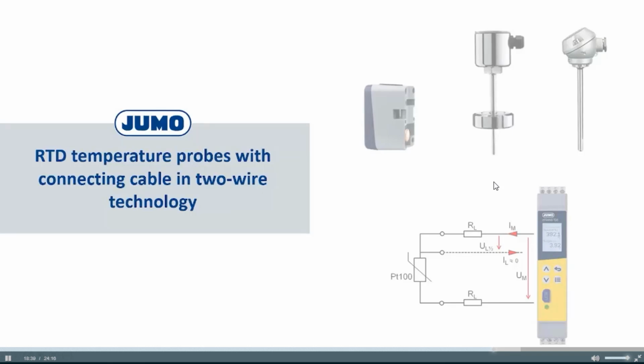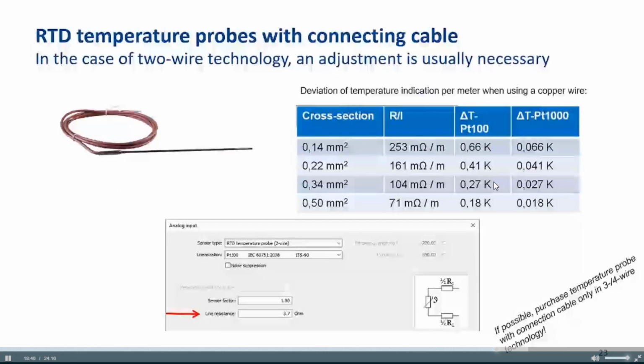Okay, if you have a temperature probe with a connection cable in 2-wire technology, this is not so good. If you have something like this, there will always be a not-so-small offset. Let's look at a copper cable with different cross sections. Here I have a small cross section, and you see the ohmic value per meter. If the cross section is small, the ohmic value per meter is high. If the cross section is bigger, then the resistance per meter goes down.